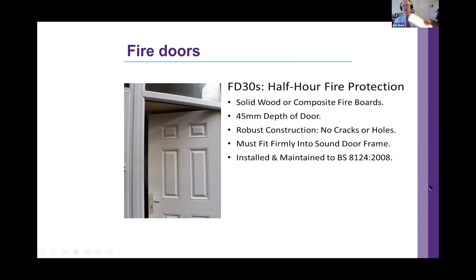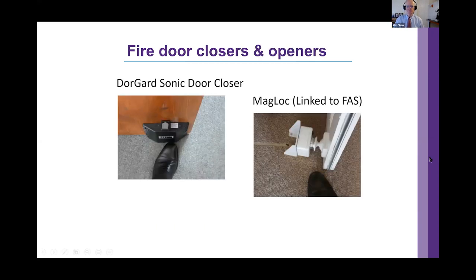It goes without saying that the glass above needs to offer a similar protection, otherwise the fire will simply go above the door. For doors, you need in some systems a door closer so the door stays open until the alarm sounds. This one is a sonic door closer — I remember it by calling it Sonic the Hedgehog. It's a DorGard — that's a type of make. And when the alarm sounds, that latch will unlatch and the door will close, provided the fire return springs above the door are working and not hanging off the wall.